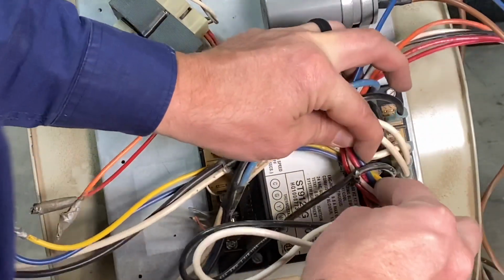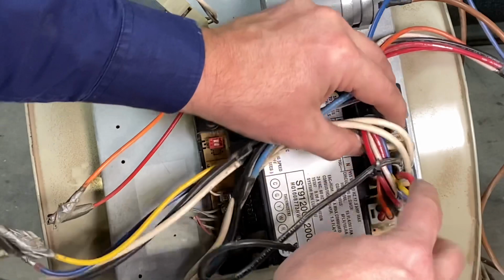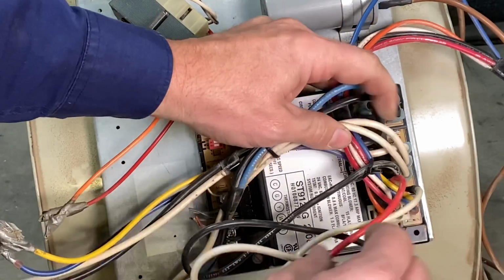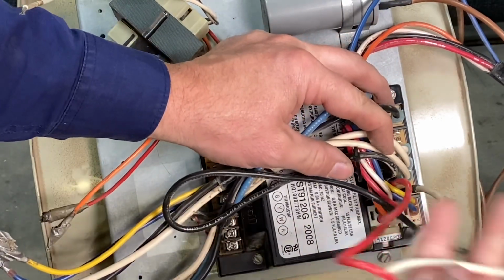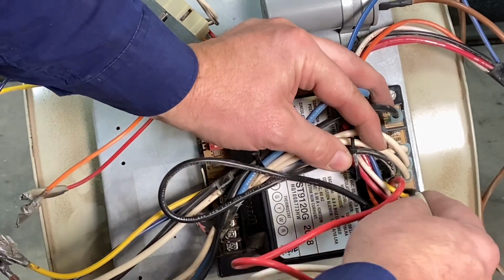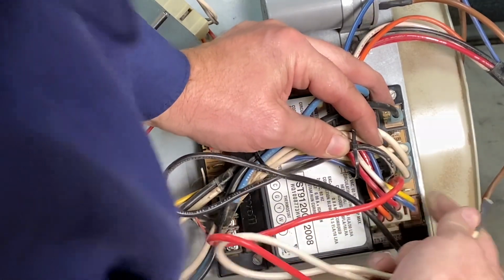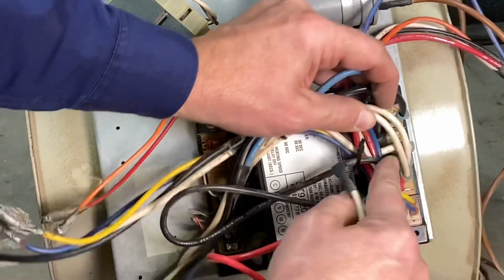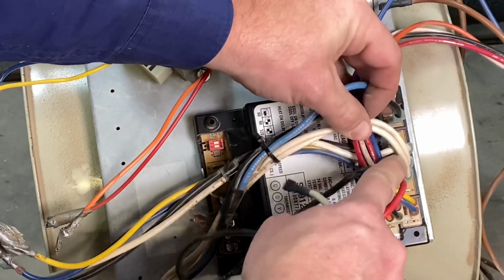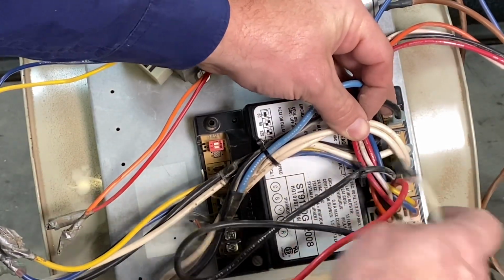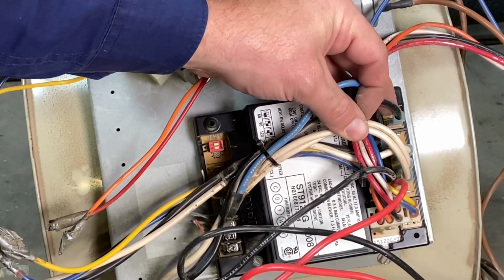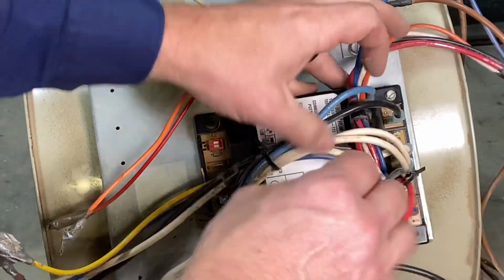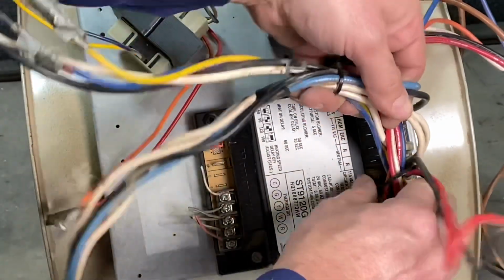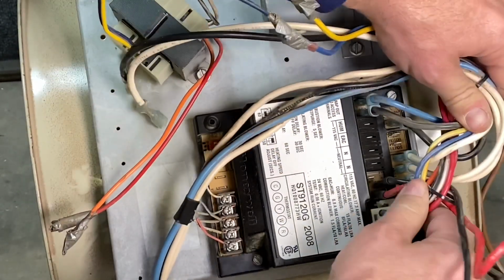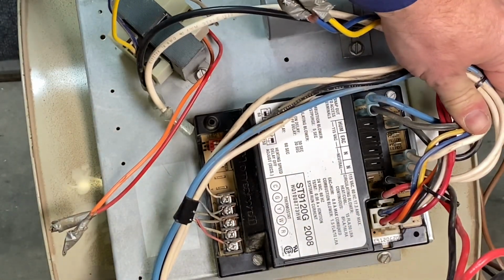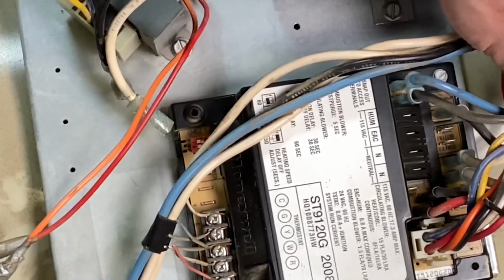So let's see where the red wire goes on the control board. It's going to be hard to see. Let's pick another wire. We have this white wire, which should be our neutral. And if we look over here, it goes to terminal number 4, and all of these are with the other white wires. You won't be able to see it just yet, but it says neutral on this control board. So that's our neutral. And then we have this black and red wire. So let's see if we can move these wires out of the way to see where they go, and let's see if we can focus in.